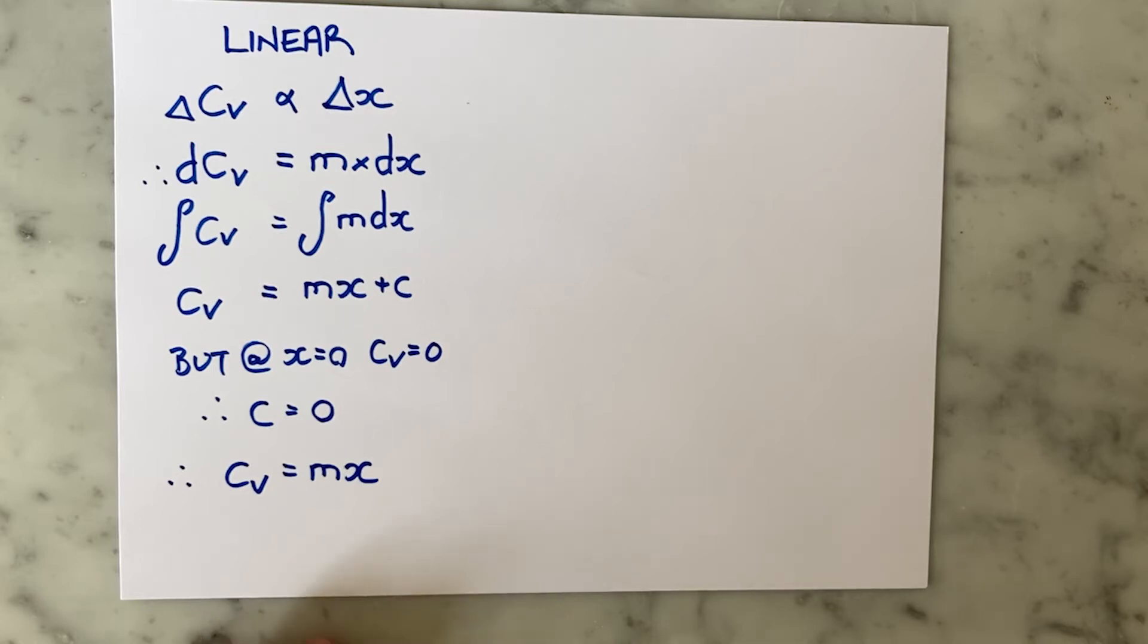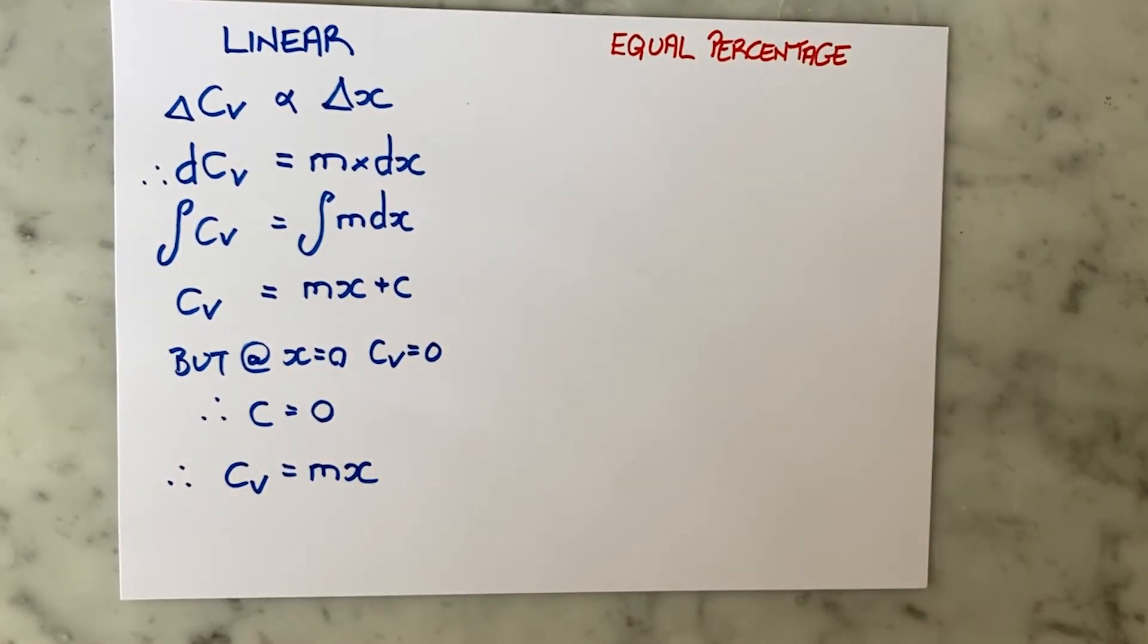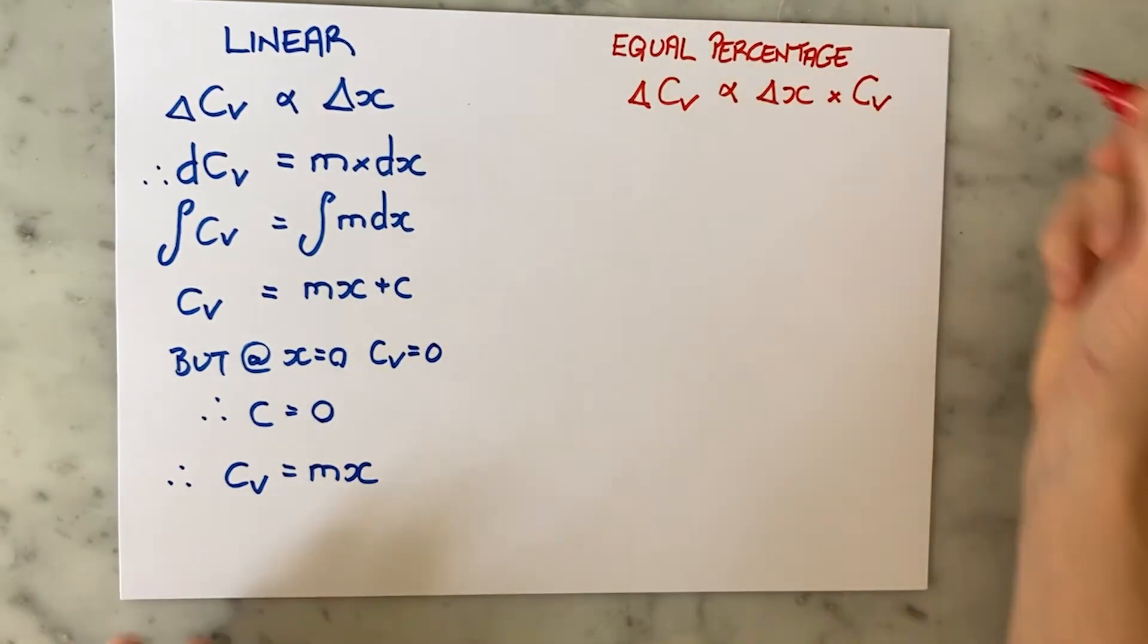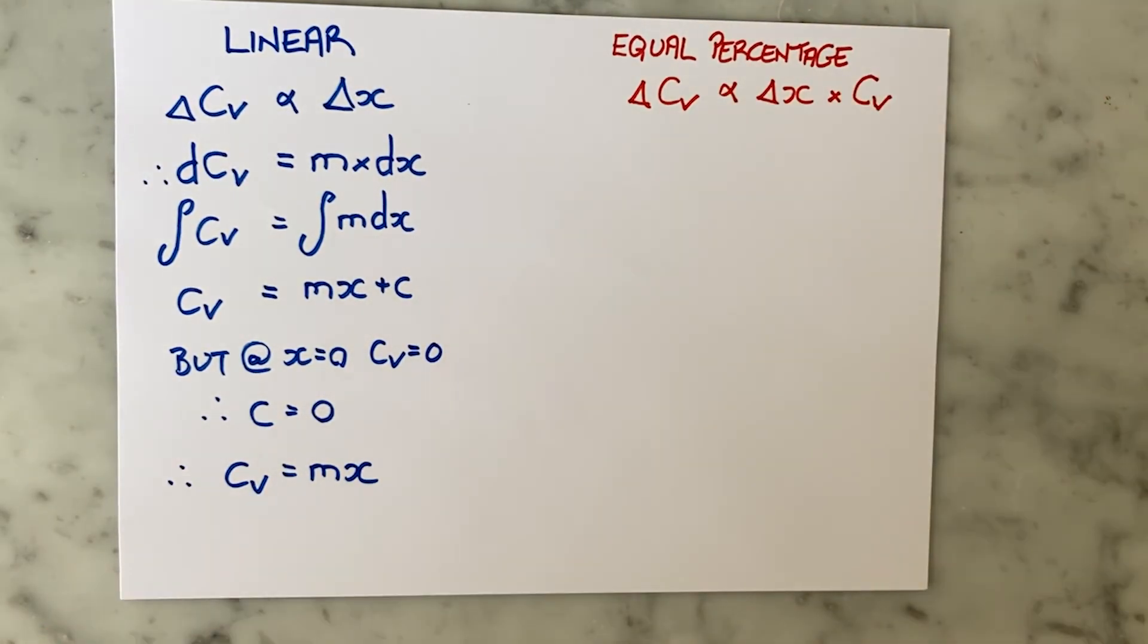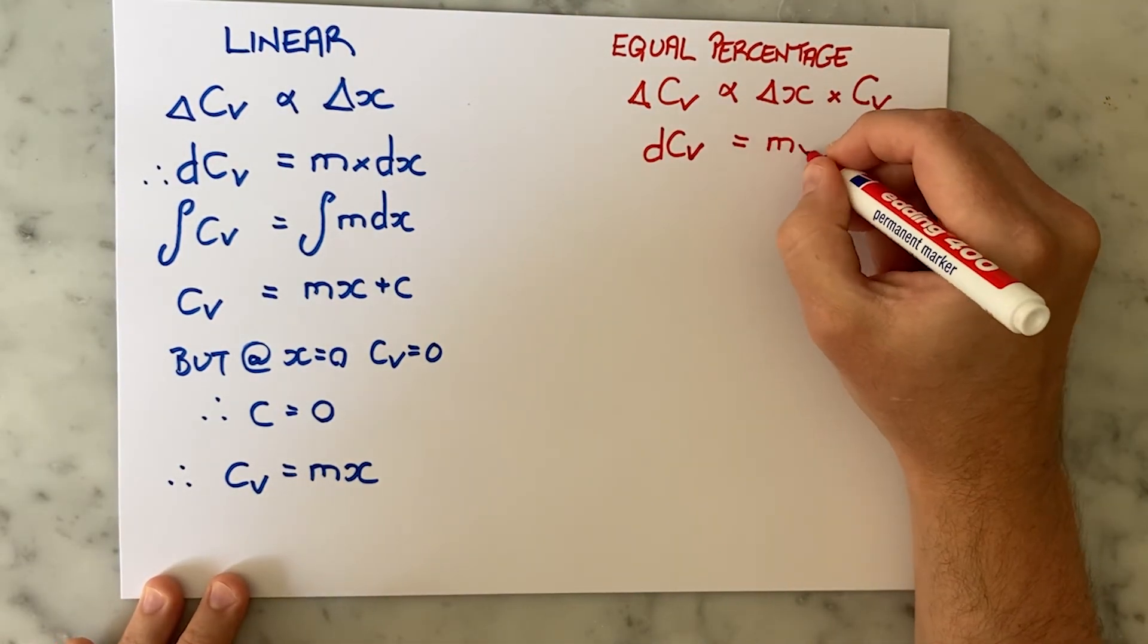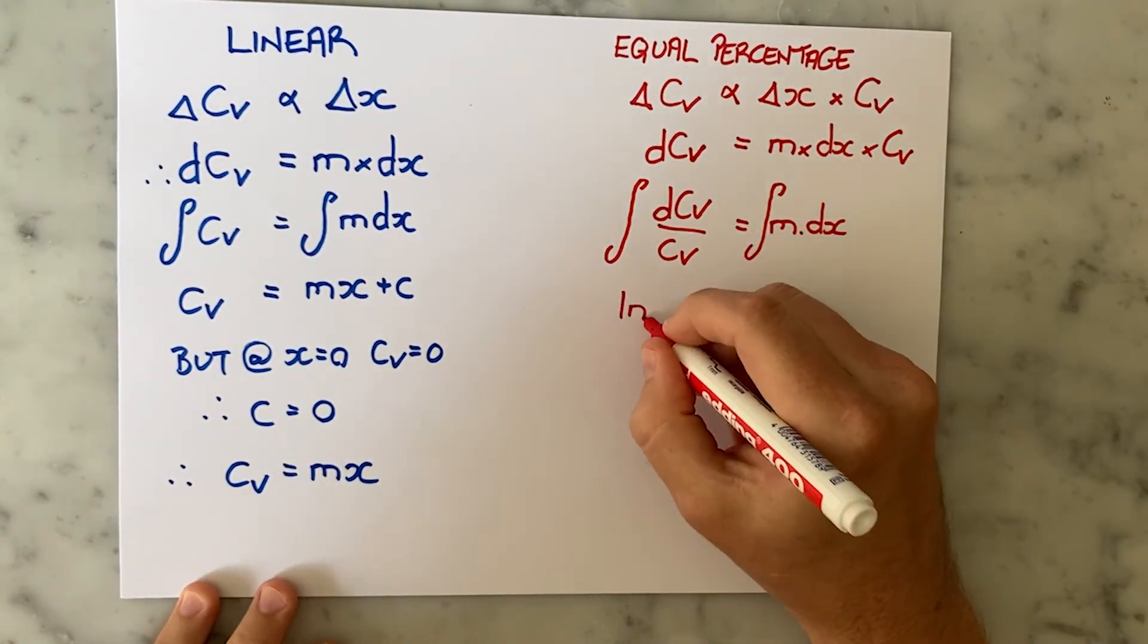For an equal percentage valve, the change in CV is proportional to the change in valve opening just like for the linear valve, but it is also proportional to the CV itself. Integrating this actually lands you with a natural logarithm of CV equaling mx + c.